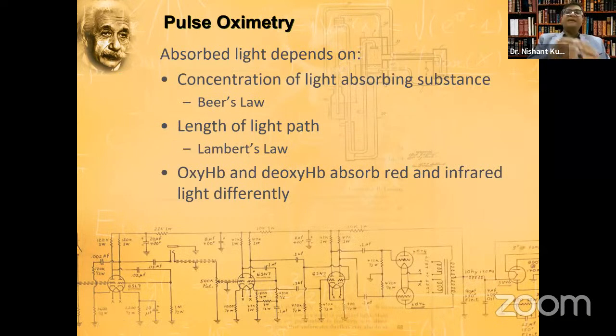Now, as I said, some of the light which is being emitted by the LED is absorbed by the finger. What exactly is absorbing the light? It is the hemoglobin. So hemoglobin absorbs the emitted light. Absorption of the light will depend on the concentration of the light absorbing substance. So the more the hemoglobin, the more light will be absorbed. And the distance the light has to travel to reach the detecting electrode will also matter: absorption will increase if it has to travel a longer path.